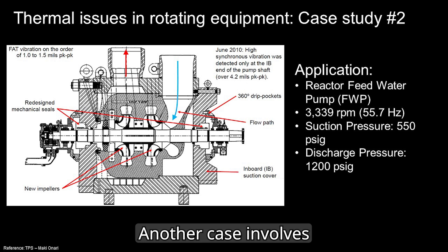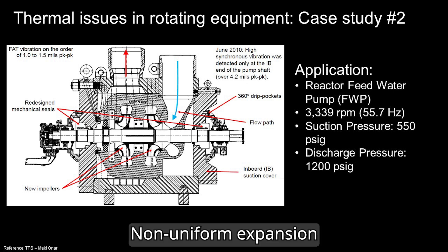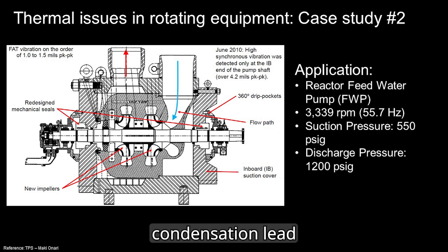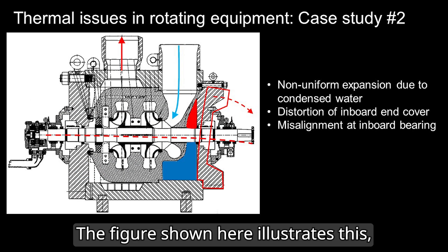Another case involves a pump suffering from similar thermal issues. Non-uniform expansion at the housing end cover caused by water condensation led to internal misalignment.